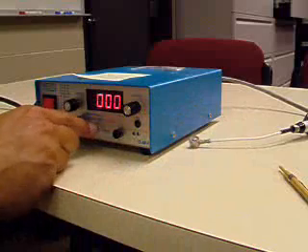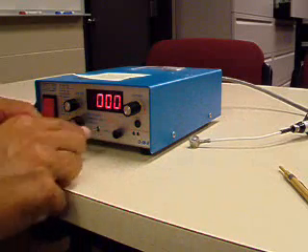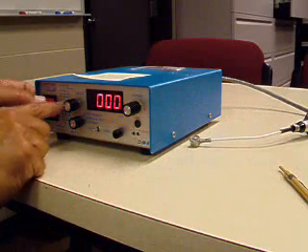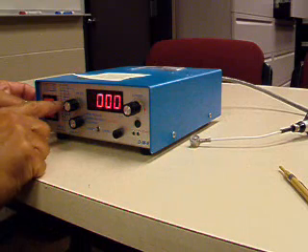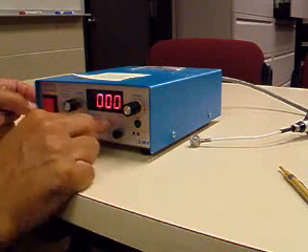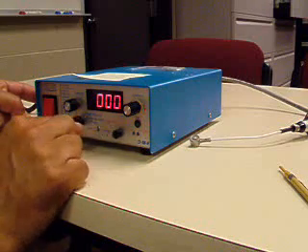When you get the unit out of the box, you have it in monitor mode. First, put it into the cal mode right here, which is the quarter inch pin on the 2,000 pound sensor. It says cal in red, and then you push it into the cal zero mode, the zero cal mode that's in red ink here also.